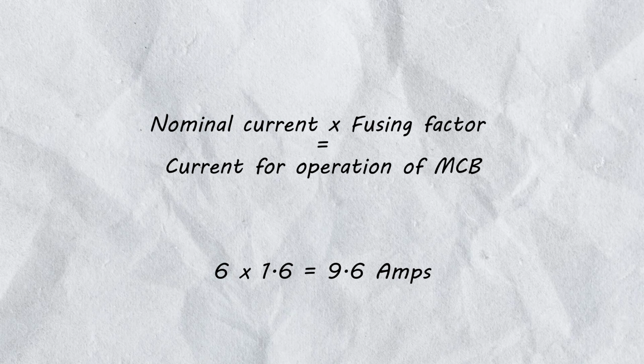If we were to just use the standard cable that we might use for every lighting situation, it might get too hot within insulated walls or bunched up with other cables that supply other circuits. So electricians calculate this tabulated value to make sure that the cable is large enough to avoid thermal issues. If you were to start considering all of the tables from the BS7671 that an electrician has to consider for all of these effects, for each one of these conditions, you start to realise there could potentially be a lot of calculations and considerations for choosing a cable.